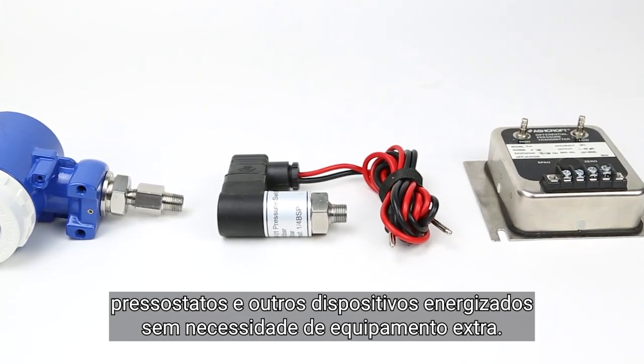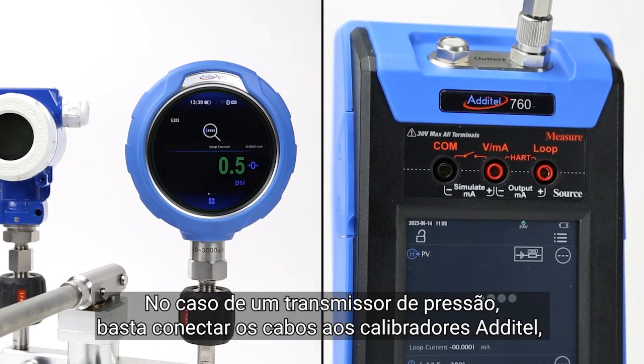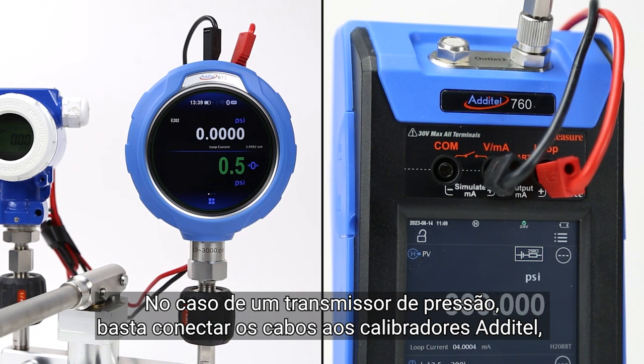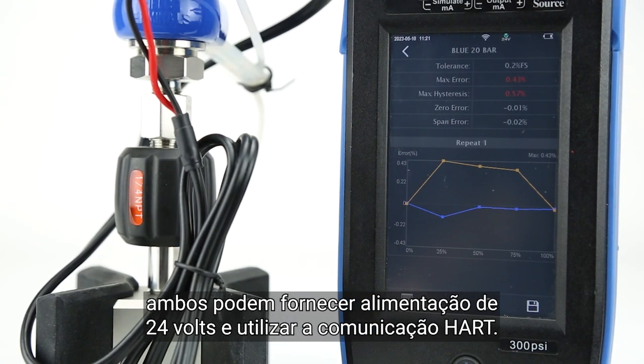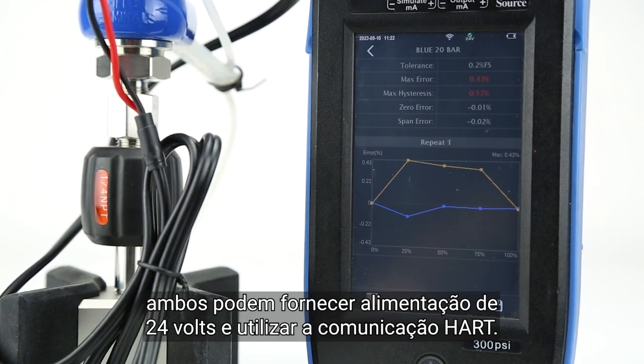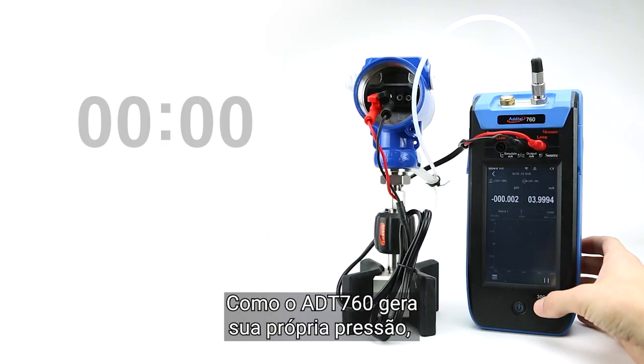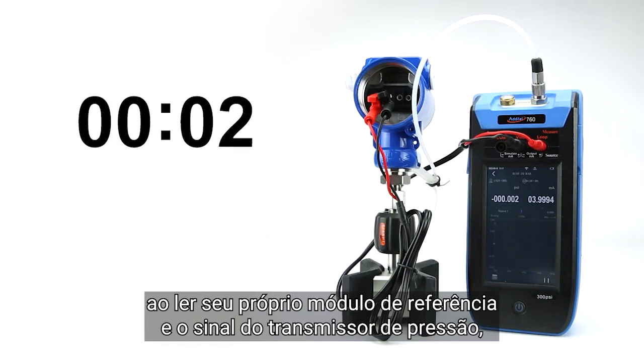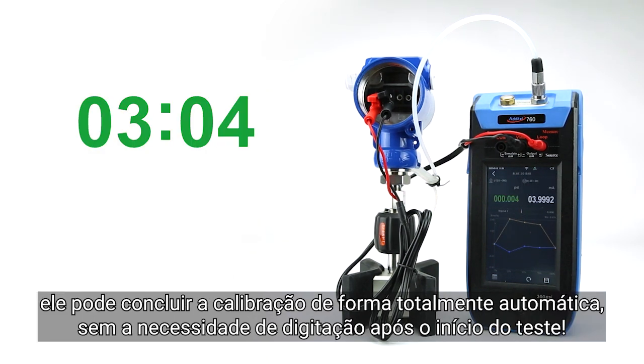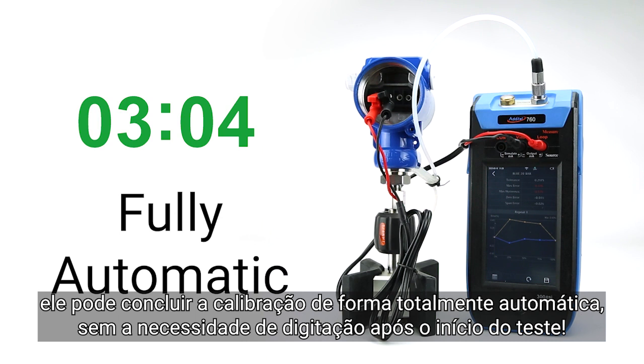extra equipment needed. In the case of a pressure transmitter, just connect the leads to the Additel calibrators, both of which can provide 24-volt power and utilize HART communication. Since the 760 generates its own pressure, while reading both its own reference module and the pressure transmitter signal, it can complete the calibration completely automatically, with no input needed after starting the test.